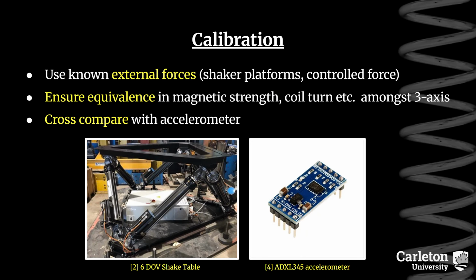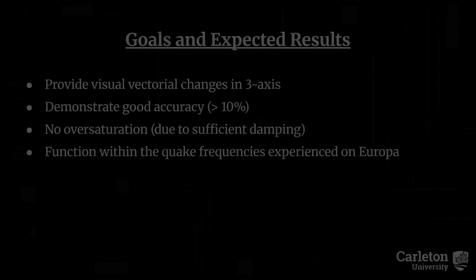The calibration of this device can be done in multiple ways. One way is to use known external forces such as forces produced by shake tables at on-campus laboratories or controlled manual displacement. Additionally, accelerometers can be temporarily used to cross-compare. To adjust for minor calibration discrepancies amongst the 3 axes, the number of coil turns of the copper can be altered.